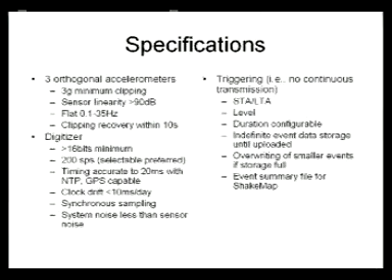If we lose the internet, then we lose timing. We don't want it to drift very much. All the samples have to be taken on the 3 sensors simultaneously. We don't want the digitizer to be any noisier than the sensor.